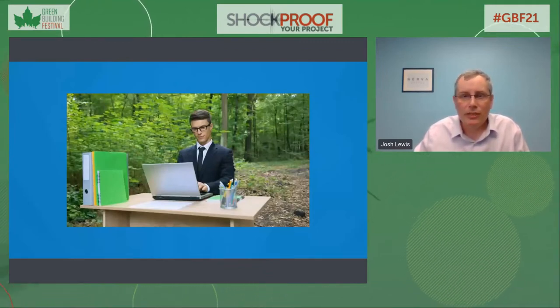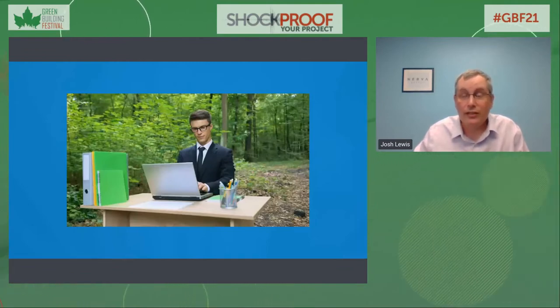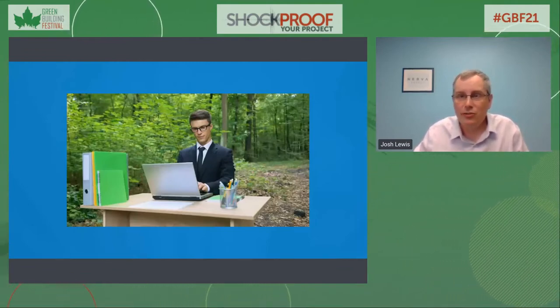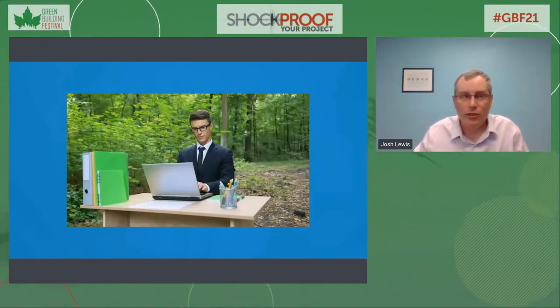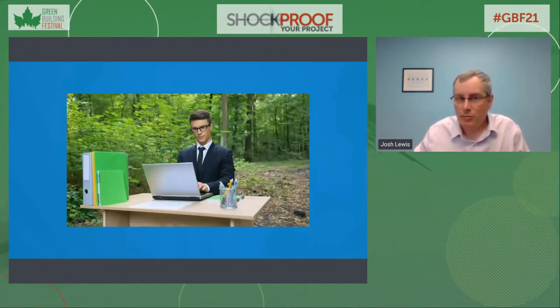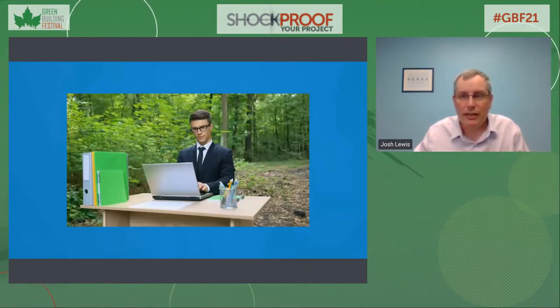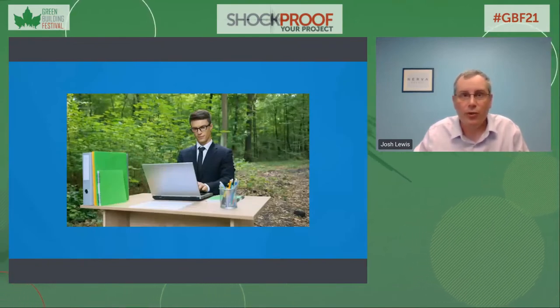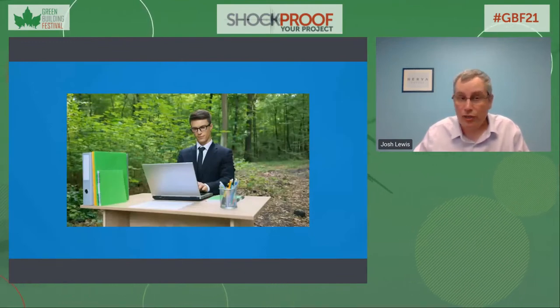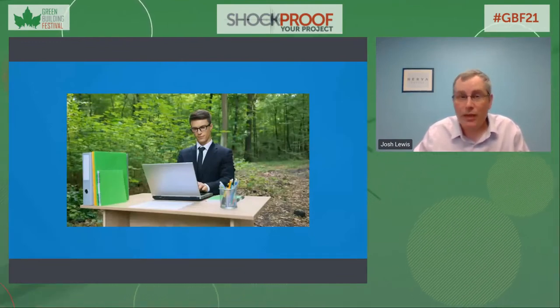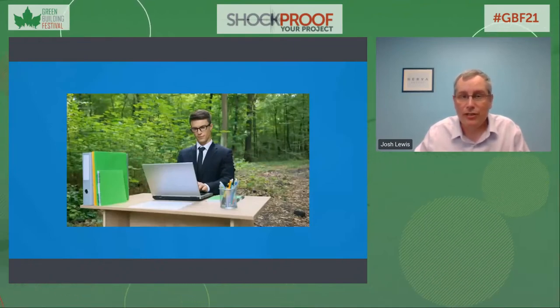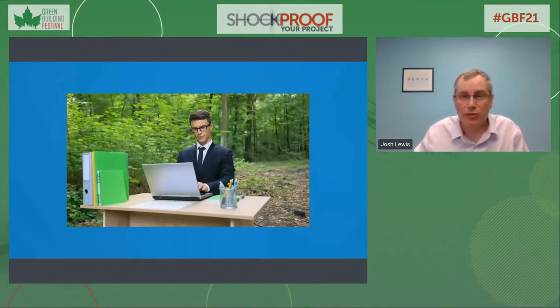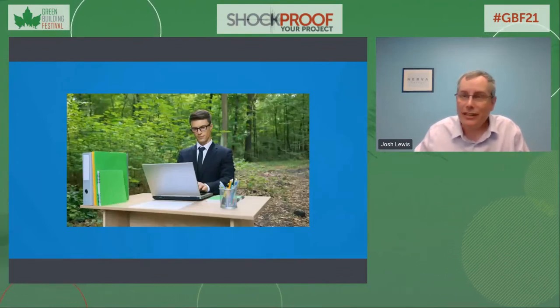It has become more common in recent times for buildings to implement demand control ventilation, which is a building automation technology that continuously measures the concentration of CO2 in the space, and based on that level, decides when to bring fresh air into the building. While this technology is mature and proven to have a large beneficial impact on energy efficiency, it can reduce indoor air quality because there can often be long stretches of hours or even days where no fresh air is being introduced. During this current pandemic, it has been highly recommended by ASHRAE and others to disable demand control ventilation systems, especially during occupied hours, in order to bring a guaranteed volume of fresh air into the building to combat aerosolized disease spread.